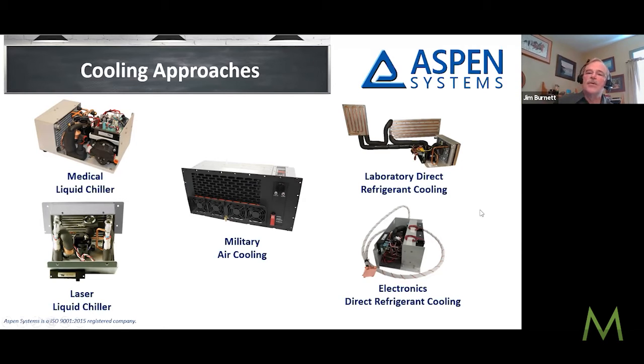The third approach we call direct refrigerant. In that case there's no pump and no liquid to maintain, so we can reach very low temperatures while eliminating some of the bill of materials from the system. For example, we can use direct refrigerant in place of a liquid chiller—no pump, no reservoir needed, lower temperatures are achievable, it's more efficient, and maintenance basically goes to zero.